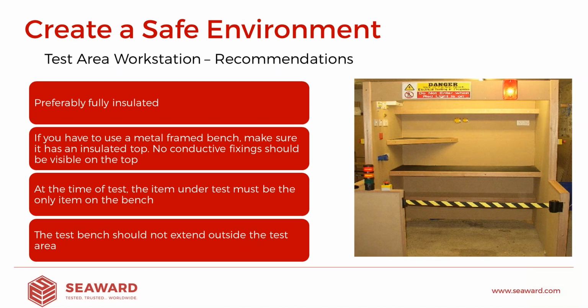So you could inadvertently create a path where current is flowing onto the legs of the bench, for example. Your operator touched them without knowing, and potentially puts himself in danger territory. Another kind of good practice when we are creating a safe working environment and training the operators is to really understand that during the time you're performing the test, it should just be the item under test and the test equipment and any kind of leads and probes that you may need to use at the time.